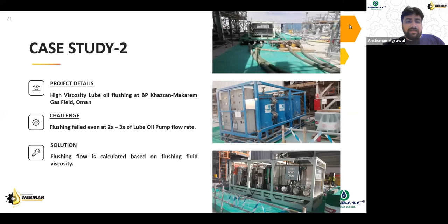What was the solution? The solution is that the flushing flow rate should not be designed based on the regular lube oil system pump, but should be designed based on the Reynolds number calculation. And if you see the Reynolds number formula, you have viscosity in the denominator. So if you have a higher viscosity, that would tend to reduce the Reynolds number. So in order to have better turbulence, you need a higher flow rate, so that the higher viscosity can be compensated through higher flow rates.